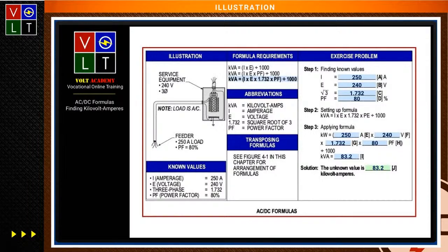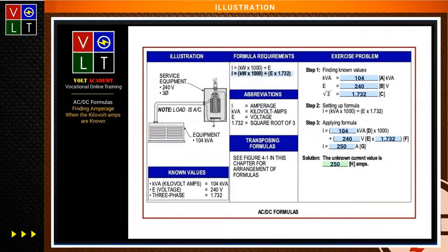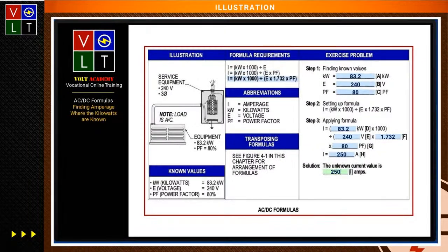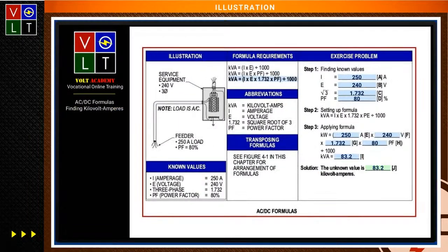And if I go back here and look at the previous problem, what did I have? Let me go back here where I'm looking at it. 83.2. You see that? Yep. Okay, let's see if I get that same value here. I take the 250 amps times 240 times 1.732 for the three-phase, and the power factor is 80%. My kVA is what? 83.2. Oh, nice. Came back out.